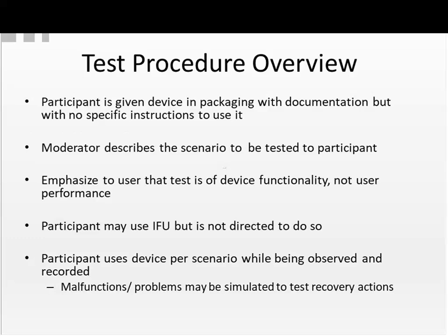It's important to emphasize to the user that the test is of device functionality, not user performance. You want the user relaxed, so he's not thinking that he's being judged, but that it is the device that's being evaluated.